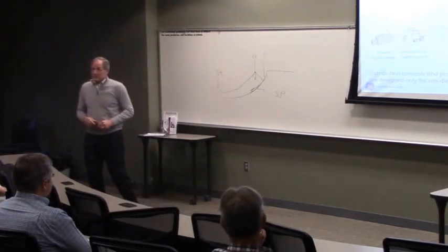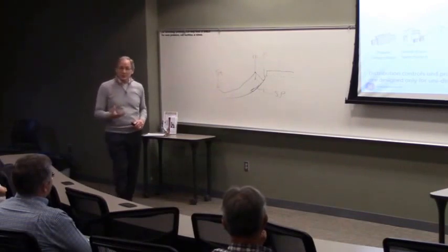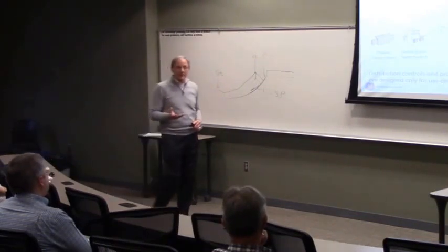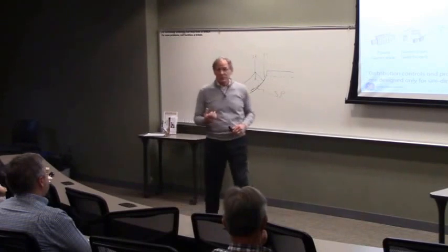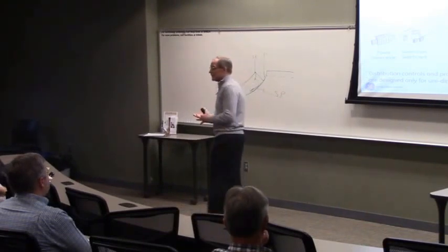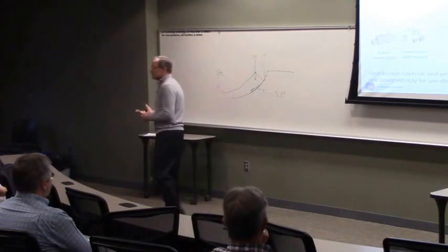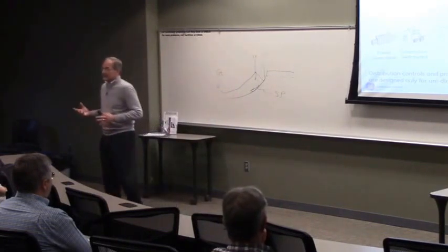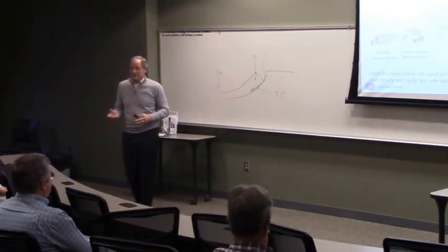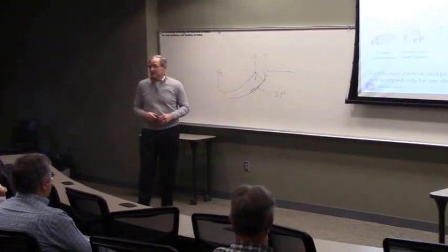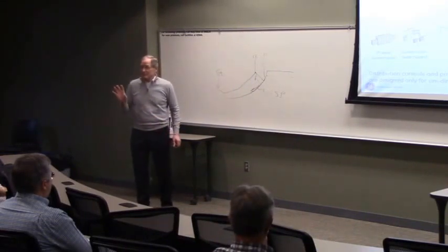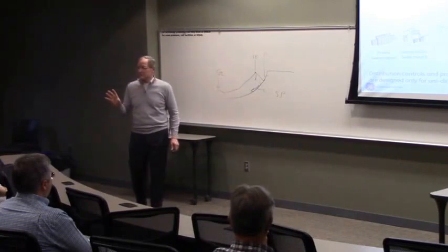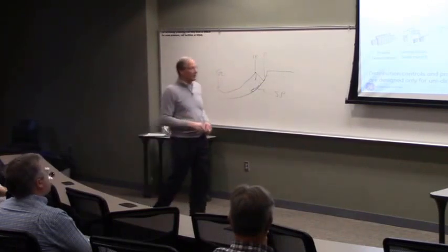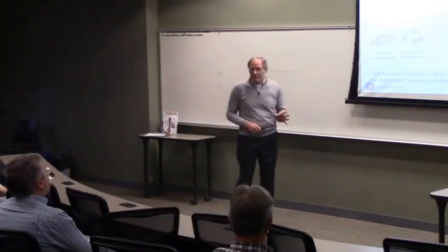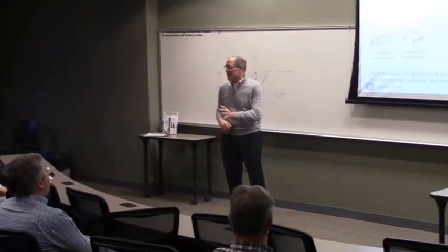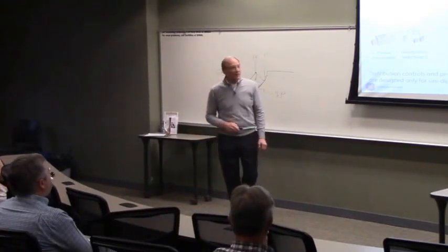Okay? And OPPD put a spec together, went out for bid, got proposals in, ordered a contract. The transformer was built, tested, brought on site. An outage was scheduled, and then it was replaced. So we never had to de-energize it. We strategically used partial discharge acoustic sensors and microprocessor-based monitoring and diagnostic equipment at the transformer to keep track of it.